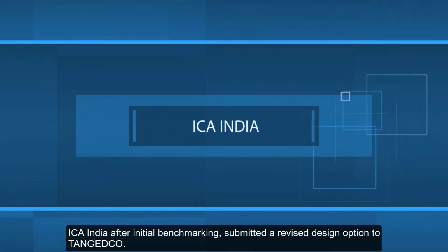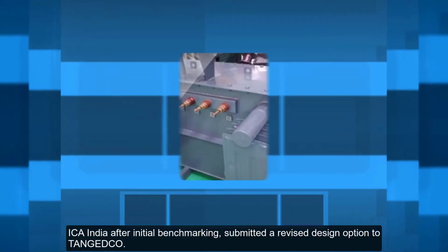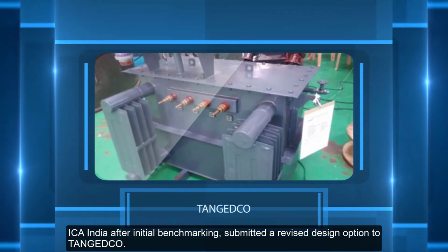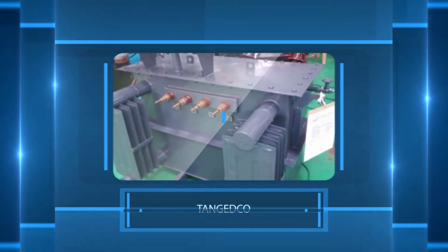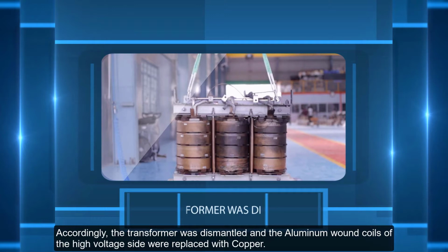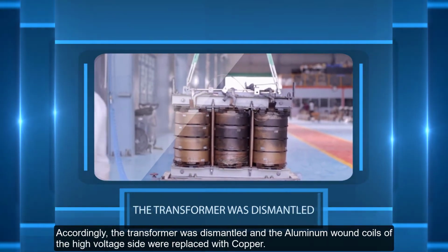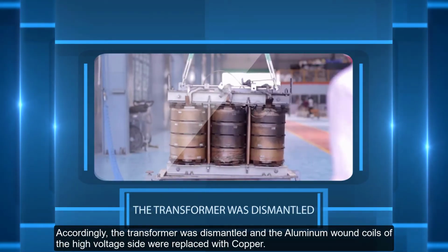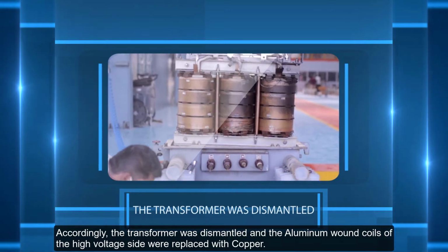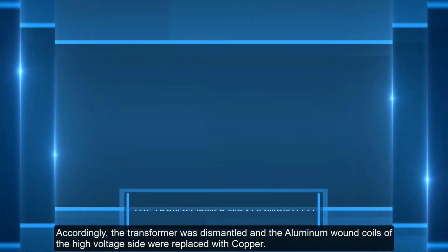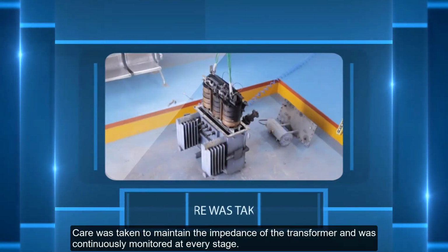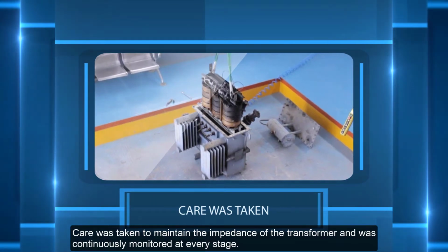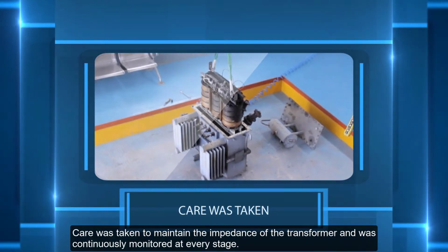ICA India, after initial benchmarking, submitted a revised design option to TANGEDCO. Once the design was approved by TANGEDCO, the transformer was dismantled and the aluminium wound coils of the high voltage side were replaced with copper as per the revised design. Care was taken to maintain the impedance of the transformer, and it was continuously monitored at every stage.